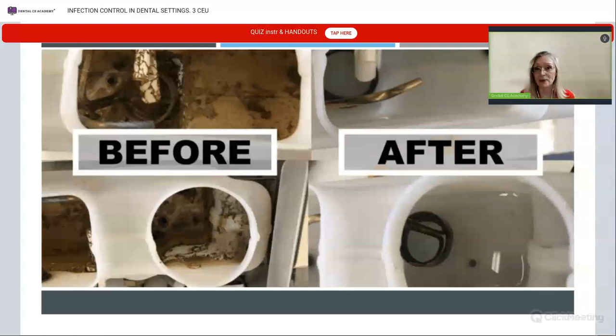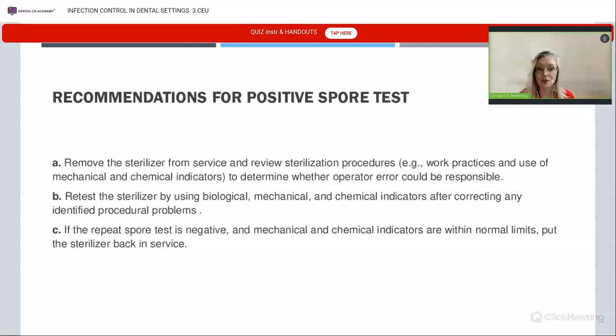I've opened up doors and I've seen this mold growing in the vinyl and so forth. Now I'm going to look a little deeper in the rest of your practice because it tells me you're taking one of the most important devices you have in your practice and you're not caring for it. So what else is going on that I need to look at, right? Recommendations for positive spore tests, repeat it. If it still comes back, then you're going to have to send the device in. And when it comes back, you'll test it with 3 empty cycles and document that.